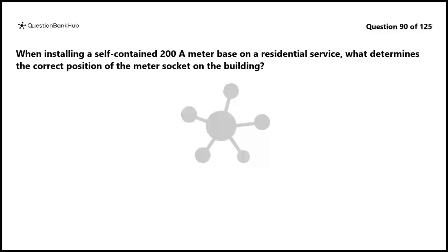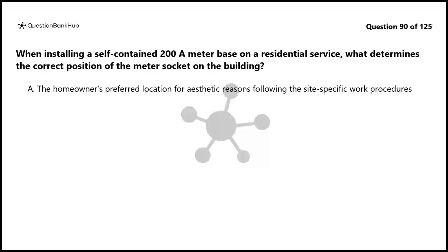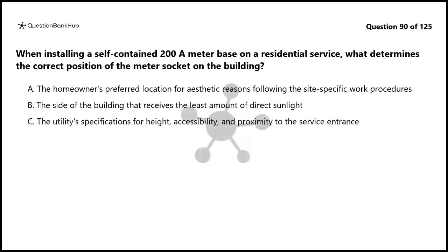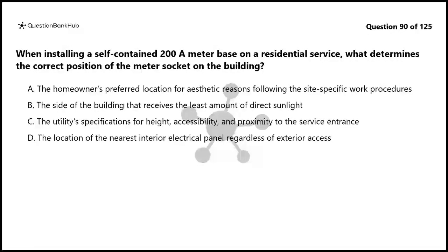Question 90. When installing a self-contained 200A meter base on a residential service, what determines the correct position of the meter socket on the building? A. The homeowner's preferred location for aesthetic reasons following the site-specific work procedures. B. The side of the building that receives the least amount of direct sunlight. C. The utility specifications for height, accessibility, and proximity to the service entrance. D. The location of the nearest interior electrical panel regardless of exterior access.